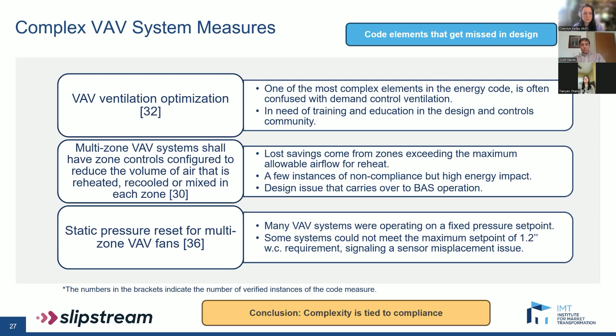So the third measure we have here is static pressure reset. We've seen that for many buildings with VAV operation, the VAVs operate on a fixed pressure set point and do not have any set point reset controls. And for the systems that did have static pressure reset controls, it also proved difficult to implement a maximum set point of 1.2 inches while still being able to supply the amount of airflow needed at the terminal units. That signals a potential sensor misplacement issue, which again may be something that got missed during the design phase and then got carried over to operation. So all 3 of these measures listed here have a common theme going on. They are considered complex elements of the code, and their level of complexity has resulted in a higher tendency of being missed during the design phase.